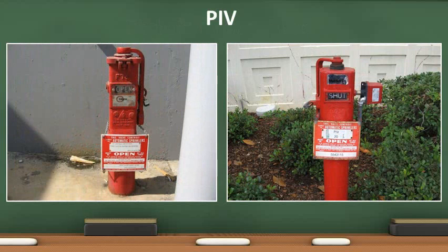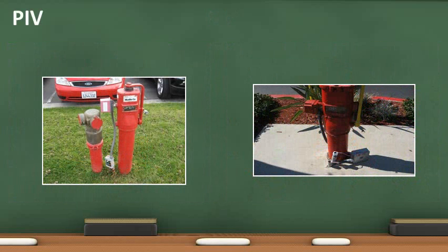These photos depict post-indicator valves, also known as PIVs. With this indicator valve type, look at the sight glass on the front to determine the valve's status. In the photo on the left, the valve is open. In the photo on the right, the valve is closed or shut. In the photo on the left, the cover for the tamper switch is missing. In the photo on the right, the J-Box has detached from the conduit. It is important to note that chains and breakaway locks are not required when there is a tamper switch installed, as in these photos.